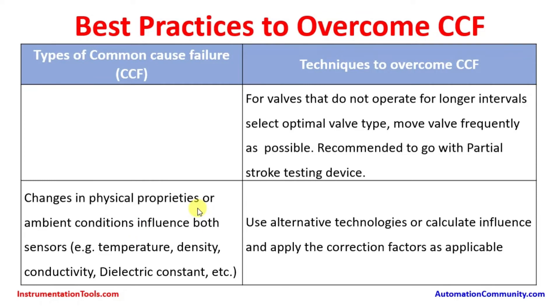Changes in physical properties or ambient conditions can influence both sensors — temperature, density, conductivity, dielectric constant, etc. Use alternative technology or calculate the influence and apply correction factors as far as possible. If temperature impacts measurement in cold environments, provide external heating. If density is a concern, provide insulation to keep fluid temperature constant so density does not impact the measurement.